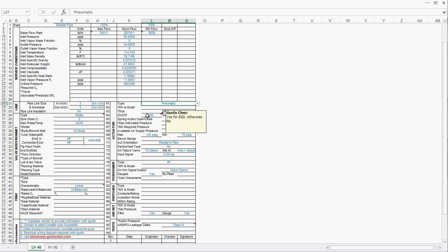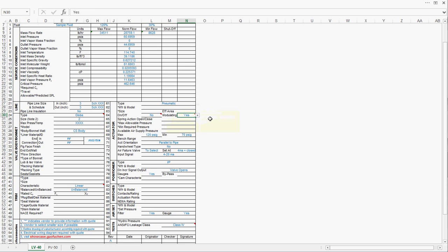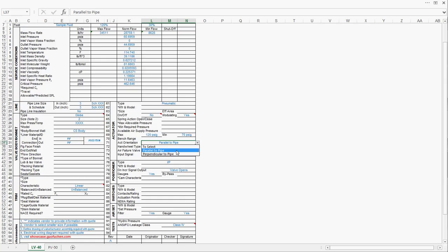Since we're talking about a control valve, it's not an on-off valve, it is going to be a modulating valve. Regarding the instrument air supply pressure, typically it is within 70 and 120 PSI gauge range. Regarding the actuator orientation, parallel to pipe or perpendicular to pipe, most of the time it's parallel to pipe to avoid any piping interference.